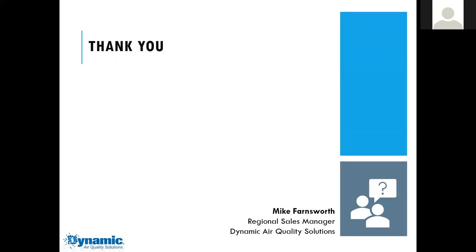So, Tim, one thing back on the conversation with PD and everything else: the vast majority of our schools and state route systems don't have the ability to accommodate a MERV 13 filtration level. And as you saw in the information Mike provided, even that MERV 13 filter's capture rate of smaller particles, really the size we're looking at for COVID and other pathogens, under 0.5 microns, is very limited. So even considering going to a panel filter with a UV light, using kind of a capture and kill, is another option to consider to provide MERV 13 plus effectiveness.